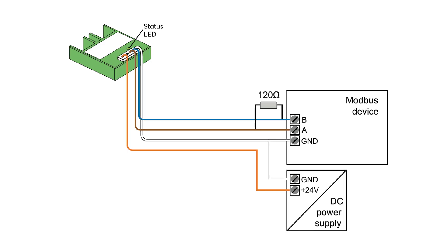With the Modbus RTU interface of the device, a Modbus device with up to 253 sensors and actuators can be integrated into the home and building automation. The baud rate and parity can be set individually. Plus, data types with 16 and 32 bits are supported.